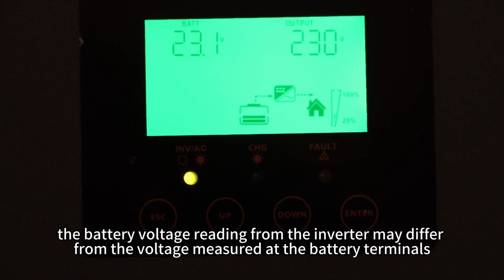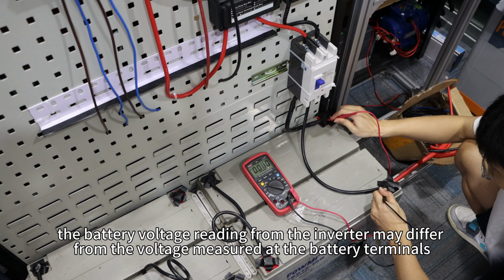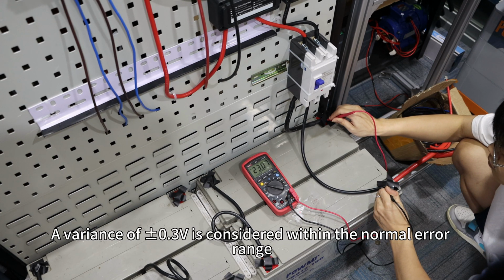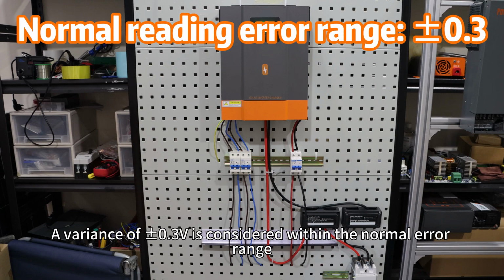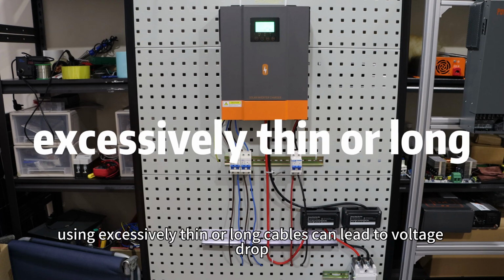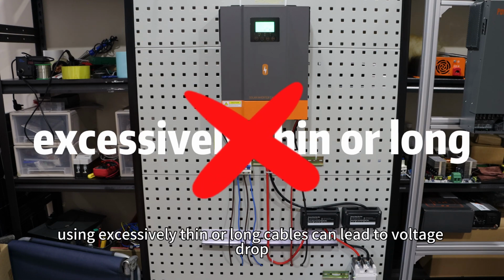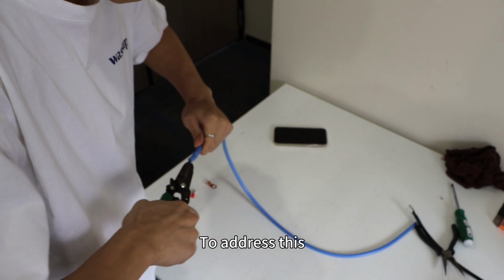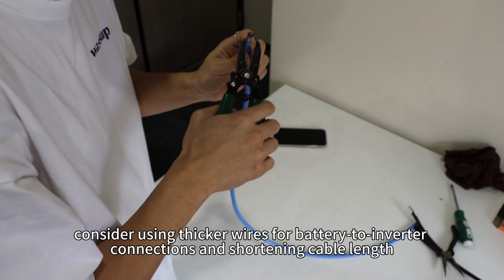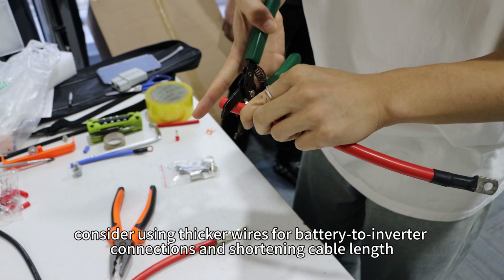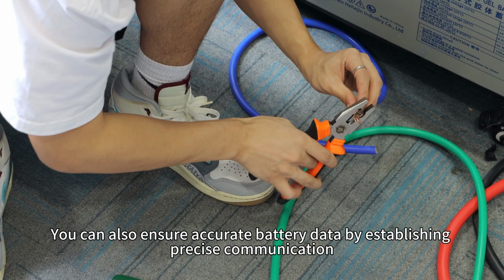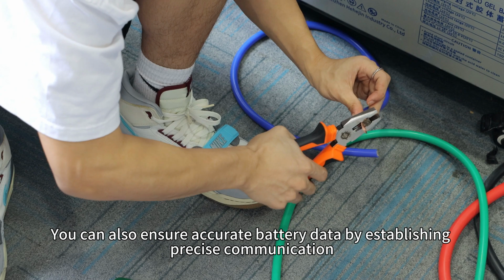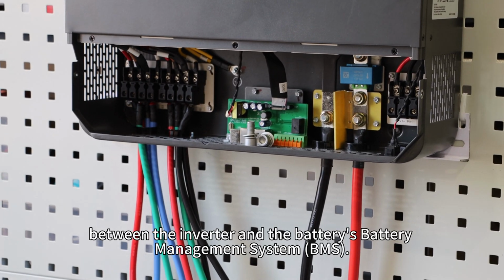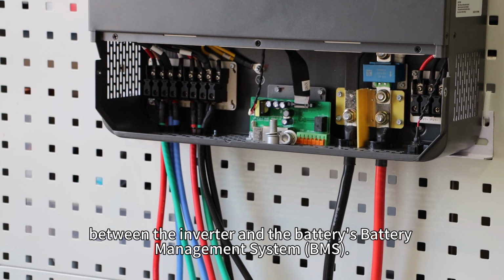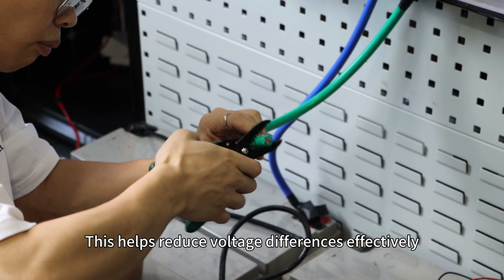Inconsistent battery voltage reading. Sometimes the battery voltage reading from the inverter may differ from the voltage measured at the battery terminals. A variance of plus or minus 0.3 volt is considered within the normal error range. Additionally, using excessively thin or long cables can lead to voltage drop. To address this, consider using thicker wires for battery to inverter connections and shortening cable length. You can also ensure accurate battery data by establishing precise communication between the inverter and the battery's battery management system. This helps reduce voltage difference effectively.